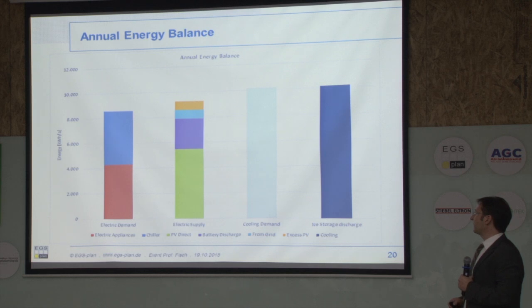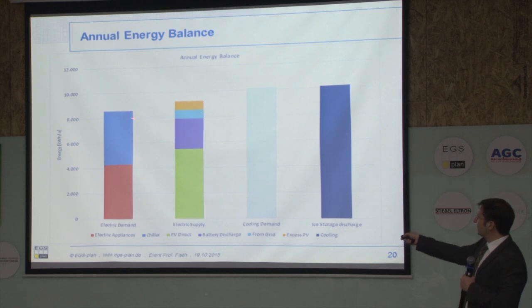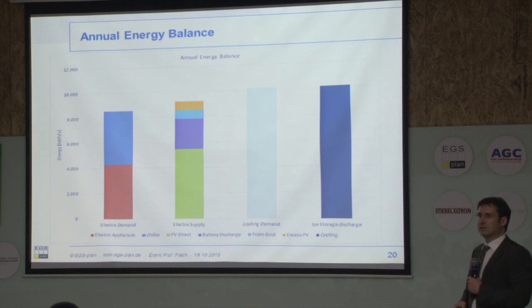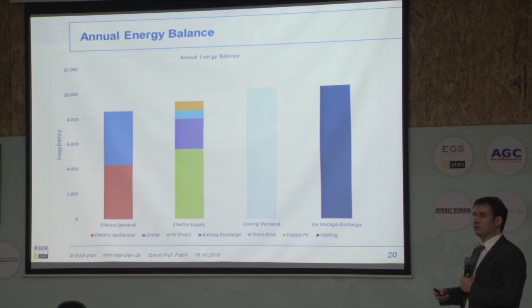The goal of our optimization of the size of the ice storage, the battery, and also the size of the PV field was to keep these two areas as small as possible. If the violet area reaches the same height as the energy demand, then you have a self-sustainable building, but that doesn't make sense from the point of economics, because then you'd need a very big battery system, big ice storage, and a big PV system, and this we want to avoid.